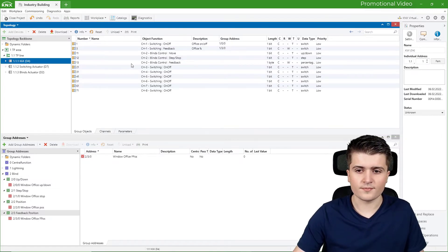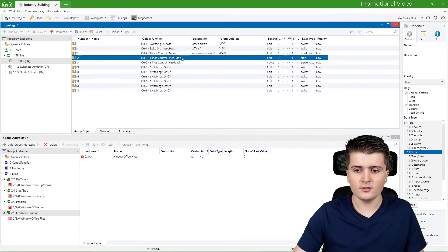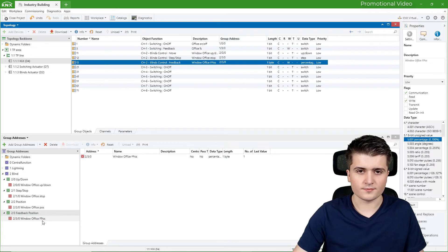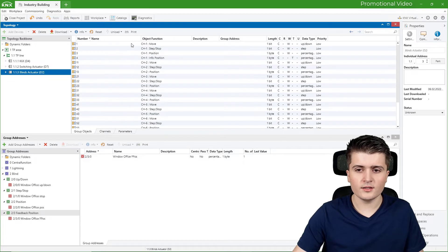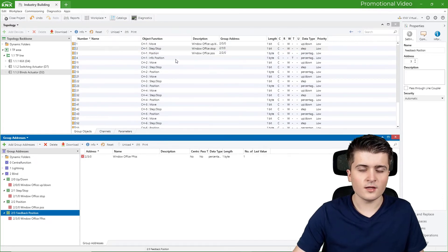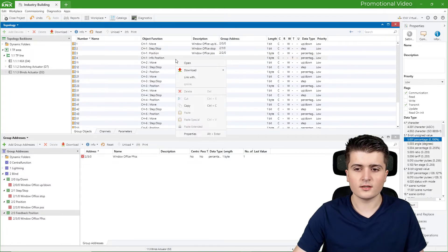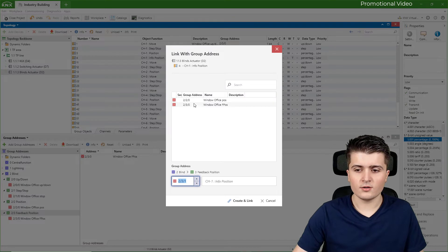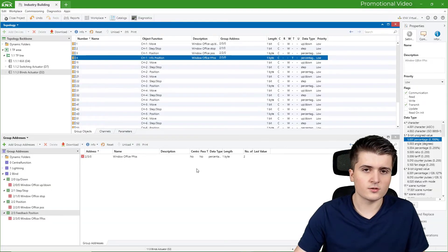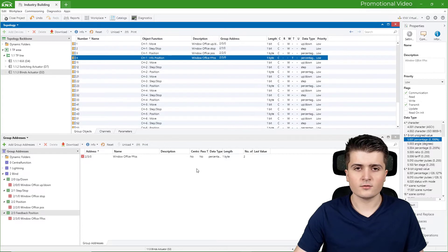Now let's hook the group addresses up to the group objects. For the push-button sensor: blind control move links to 'Up Down', step/stop links to 'Step Stop', and feedback links to 'Feedback Position'. For the blind actuator: move links to 'Up Down', step/stop to 'Stop', and position to 'Position'. You can also right-click a group object, choose 'Link with', and select from the available group addresses — for example linking the feedback position address 2/3/0.